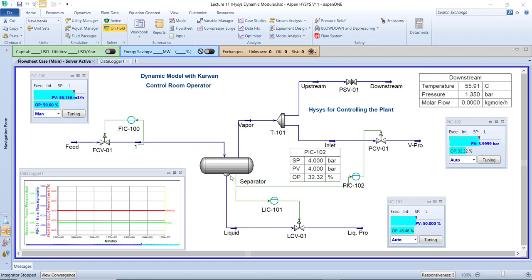At four bar there is no heavy hydrocarbon carryover from the vapor line. But if the pressure drops to three or two bar, you lose some heavy hydrocarbons — reducing the pressure permits some heavy hydrocarbons to escape through the vapor line. For that reason, you must have special equipment to control the pressure continuously at the same set pressure, because the plant runs 24 hours. If you can't control the pressure, the temperature, and the level, you lose the quality and quantity of your products.